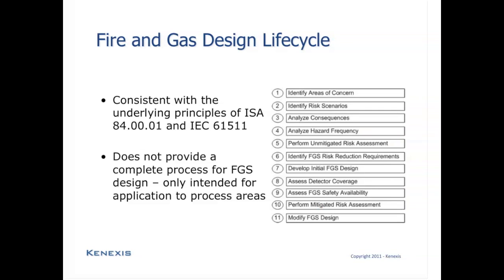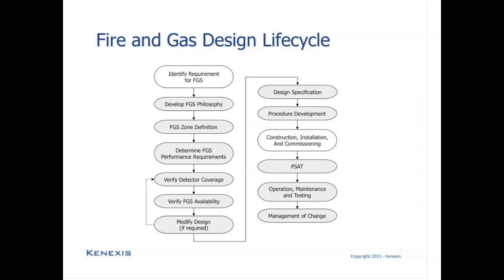Okay. Now, the ISA 84 technical report is going to be consistent with the underlying principles of the IEC 61511 standard and also the ISA 84.00.01 standard, which is essentially the same. Now, this process does not provide a complete guidance process. It doesn't provide a complete process for fire and gas system design. It is only intended for application to process areas. Areas of occupied buildings are still going to need to conform with the prescriptive standards that are applicable in that jurisdiction, such as NFPA 72, if your facility is going to be located in the United States.